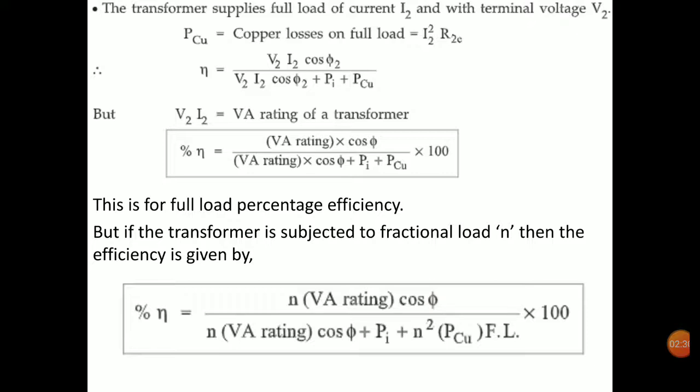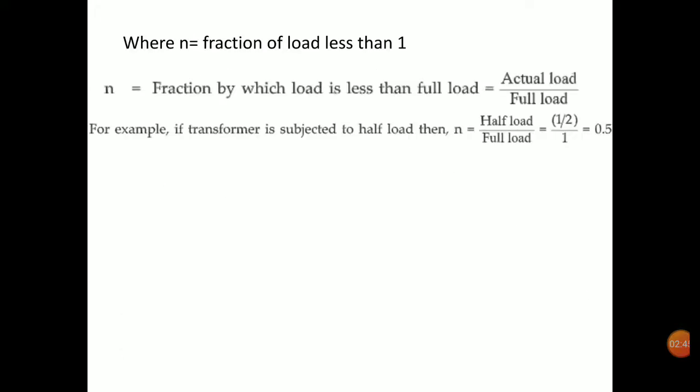The iron loss is a constant loss — it remains constant irrespective of the load — whereas the copper loss varies as the load varies. That is why we get the term n² times Pcu full load. Here n is the fraction of load, defined as actual load divided by full load. For half load, n equals 0.5, and for three-fourth load, n equals 0.75.